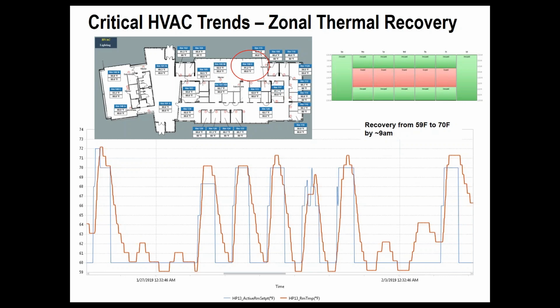and what we saw was that there was decent recovery on the north open office area, where we were recovering from the setback temperature of 59 up to 70 by 9 a.m. The schedule's really 7 a.m. So I do think there's an opportunity to improve this morning warm-up scheme. But if you're recovering by 9 a.m., to me, that's pretty good, and we're doing a good job of our morning warm-up. Although there is some opportunity for tuning there.